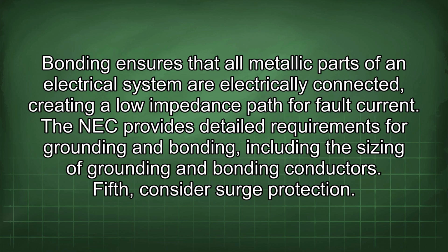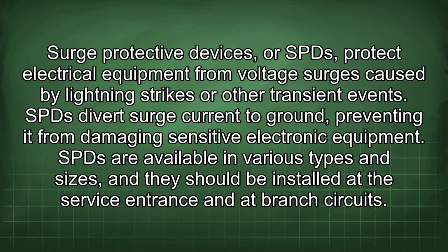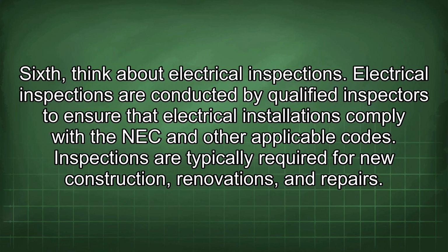Fifth, consider surge protection. Surge protective devices, or SPDs, protect electrical equipment from voltage surges caused by lightning strikes or other transient events. An SPD diverts surge current to ground, preventing it from damaging sensitive electronic equipment. SPDs are available in various types and sizes, and they should be installed at the service entrance and at branch circuits.